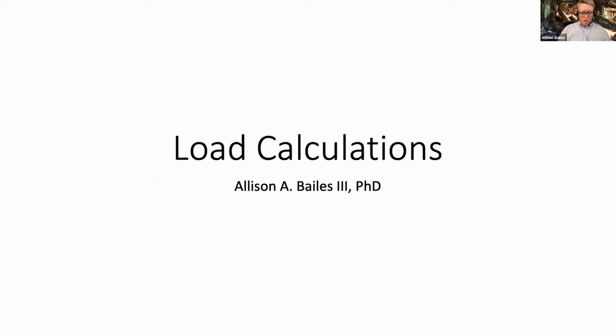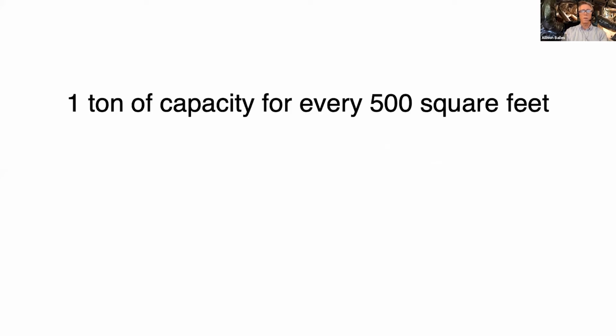All right, so I'm going to talk just about load calculations. Mark kind of mixed in a little bit of load calculations and energy modeling, and I believe Ed is going to go after me and talk about energy modeling. The difference between energy modeling and load calculations is basically the time scale. Load calculations give you the peak heating and cooling needs for the building so you can size the mechanical equipment—the heating system, the cooling system. Energy modeling tells you how much energy that building is going to use over a longer time span, usually a year. That feeds into programs, certifications, and energy modeling numbers like the HERS index, and Passive House has its own tools and metrics. But with load calculations, it's all about the peak heating and cooling needs so you can get the mechanical equipment right. So here's how you do it.